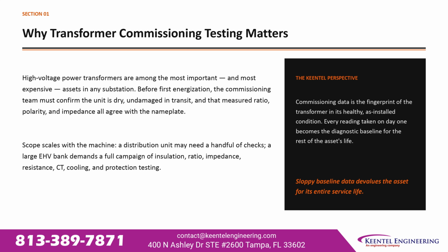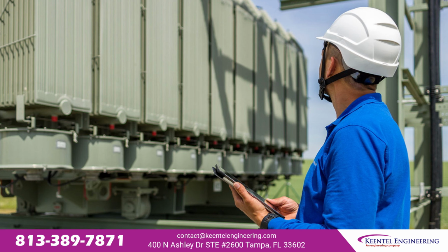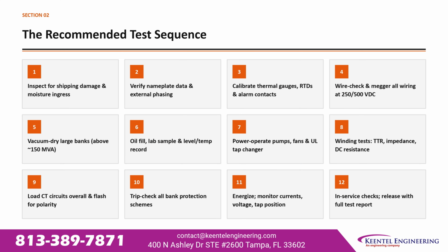Here's the perspective worth holding on to. Commissioning data is the fingerprint of the transformer in its healthy as-installed condition. Every reading taken on day 1 becomes the diagnostic baseline for the rest of the asset's life. Sloppy baseline data devalues that asset for its entire service life. 12 steps make up the recommended sequence.